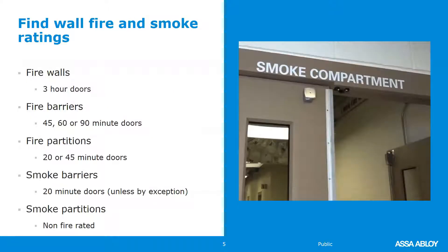Use the life safety plans to find fire walls and smoke ratings. If firewalls — each one of these has a distinct definition in the International Building Code. Firewalls are going to be three-hour doors. Fire barriers will be either 45, 60, or 90-minute doors. If they're part of an exit enclosure, they're going to be 60 or 90-minute. If they are more like a storage room, it would be the 45-minute type. Fire partitions: you'll find either 20 or 45-minute rated doors, depending on the location within the building and what is being protected.